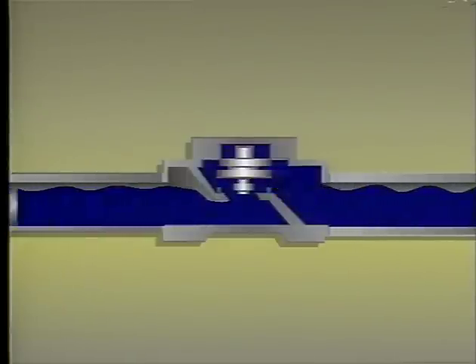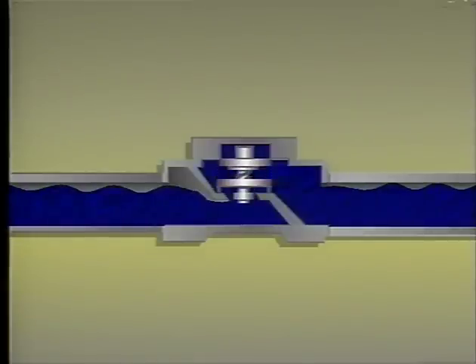These valves also use a spring to help in closing. The result is that silent check valves are closed by the loss of upstream pressure rather than the reversal of flow, preventing hydraulic shock.